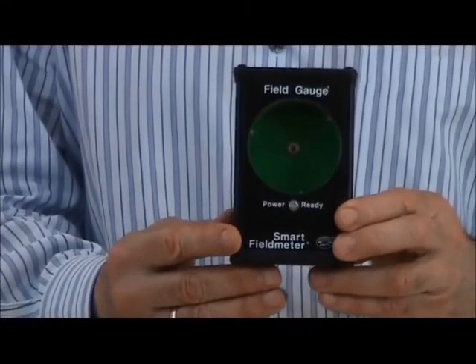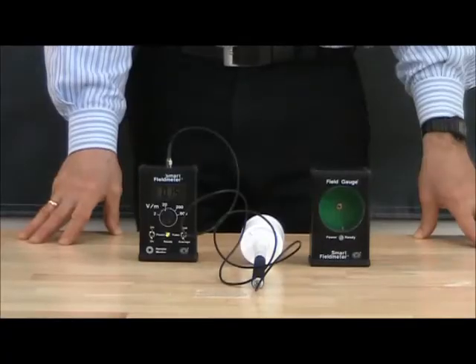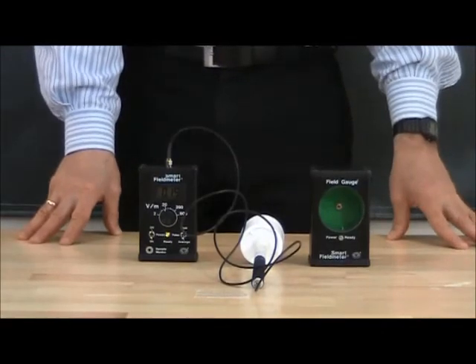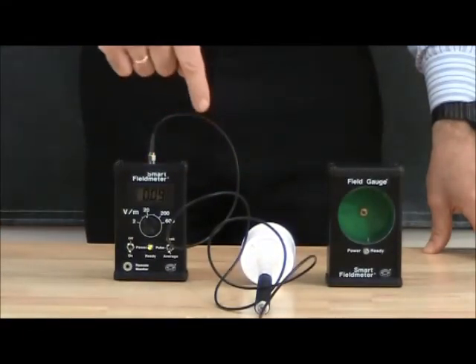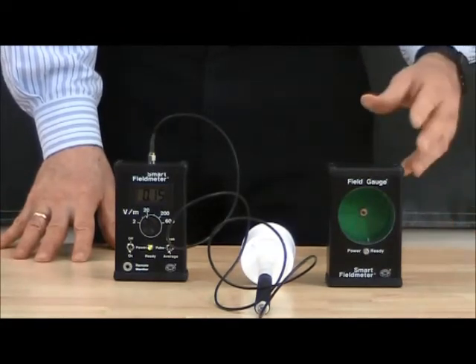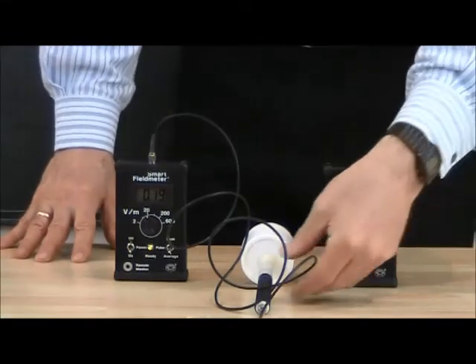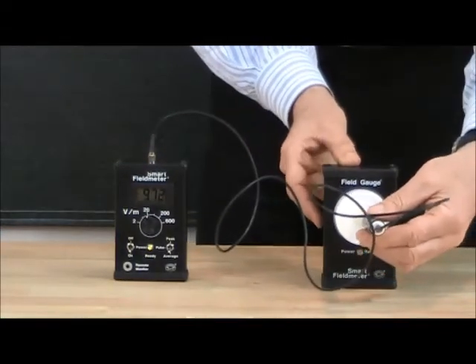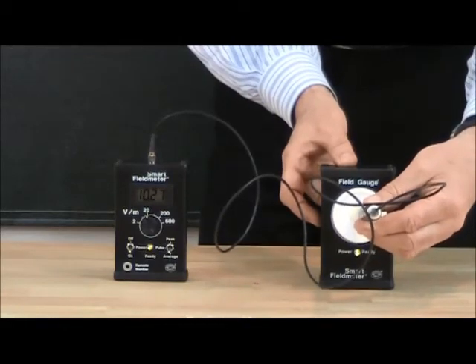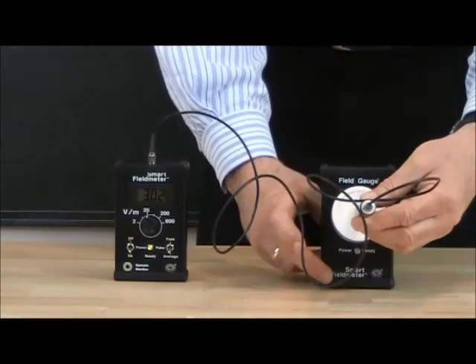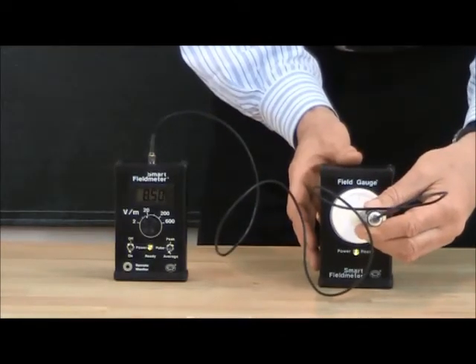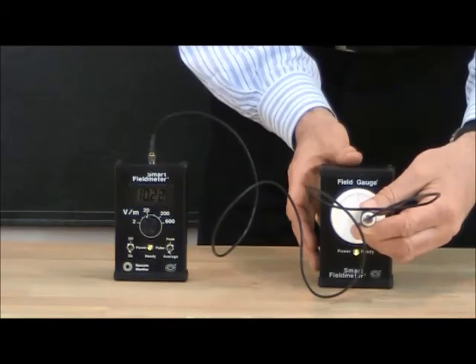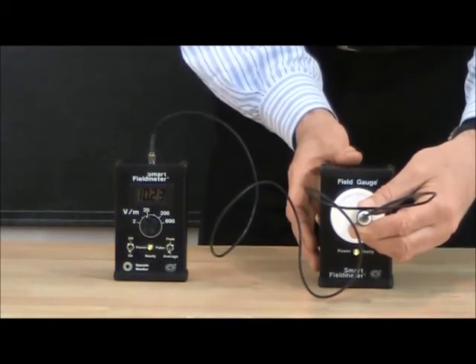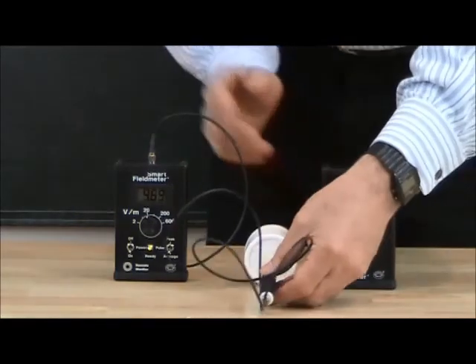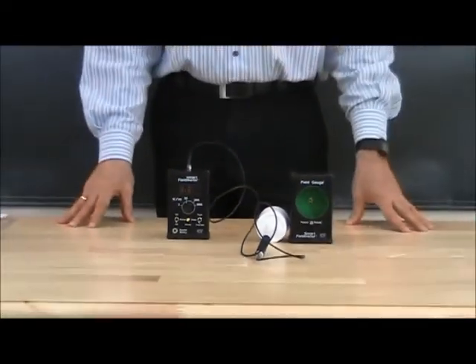With every broadband kit that we sell, we supply another component. This component is called a field gauge. The field gauge allows you to test the operation of your meter, probe and quality of the interconnecting cable right in the field in a second. Operation of the field gauge is extremely simple. You take a probe and plug it into the opening of the field gauge, and you push a little bit until you feel that the switch turns on and you see a green LED. At this moment you read what the display shows. Typically this is a reading of about 10 volts per meter, and this reading is specific for your meter and probe, and we will supply this reading when we calibrate the unit.